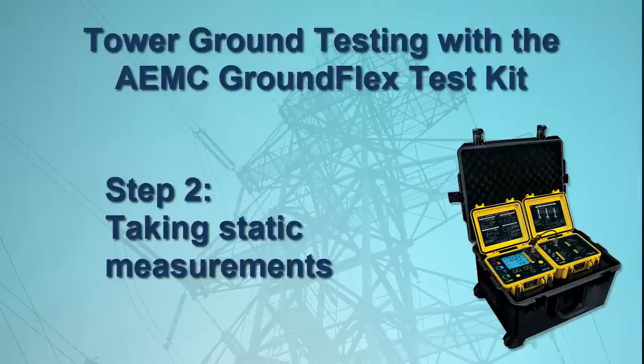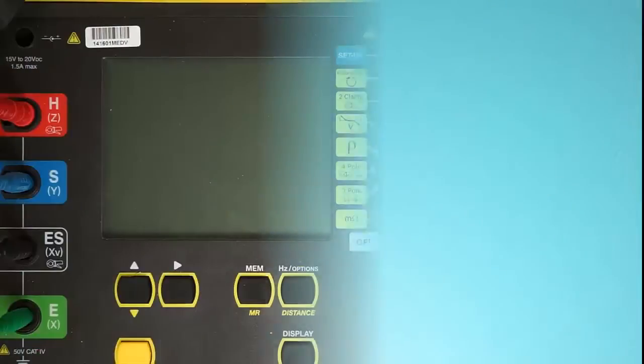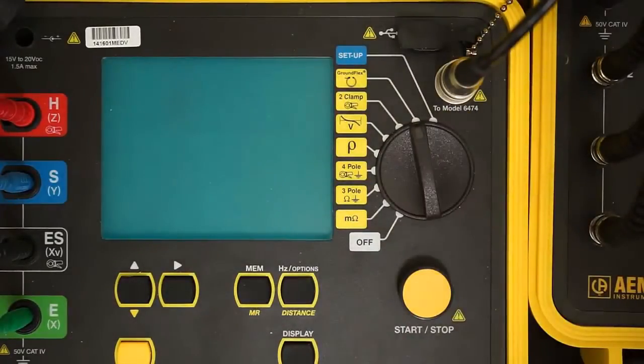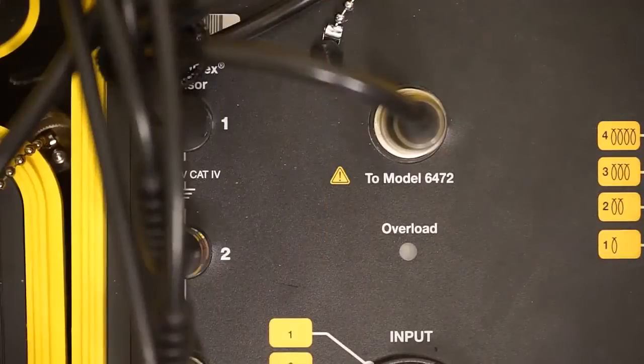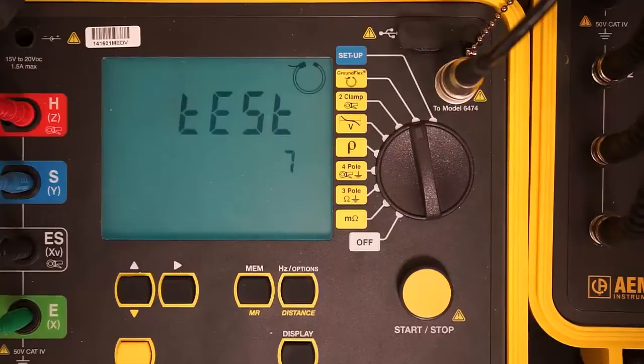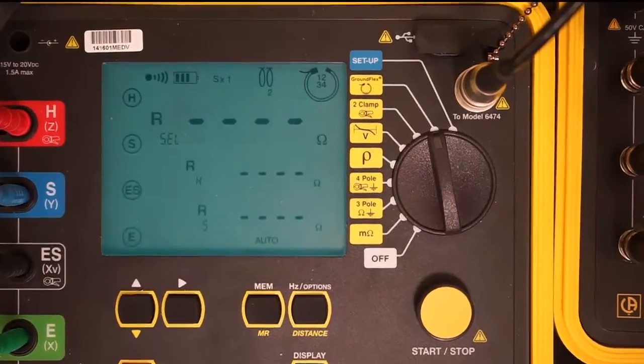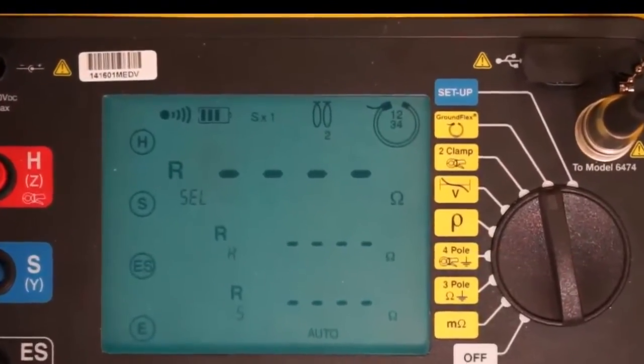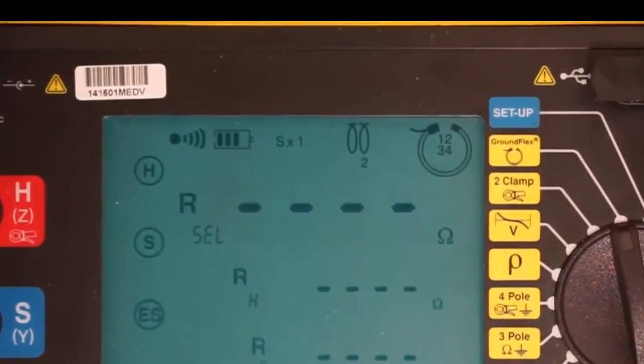We'll start by obtaining static data that does not require an output current. This static data will help identify whether or not we need to make any adjustments to our setup before performing dynamic tests. Turn the dial on the Model 6472 to the GroundFlex setting. The instrument performs a series of self-calibration tests, during which the red overload LED light on the Model 6474 may light up briefly. When this is finished, check the row of icons at the top of the display screen and ensure they match your test configuration.